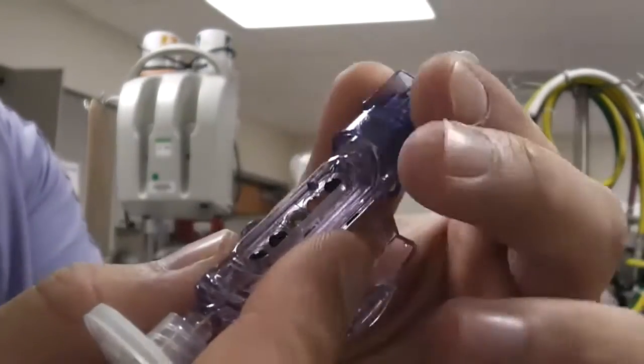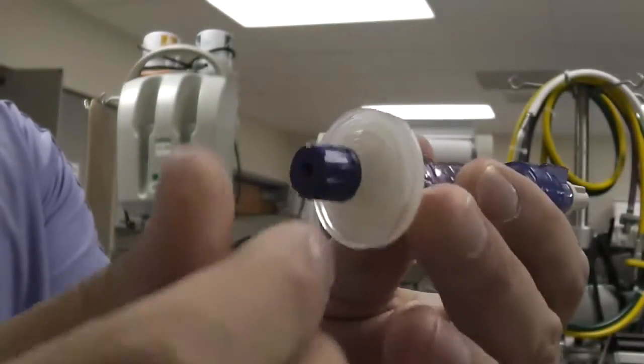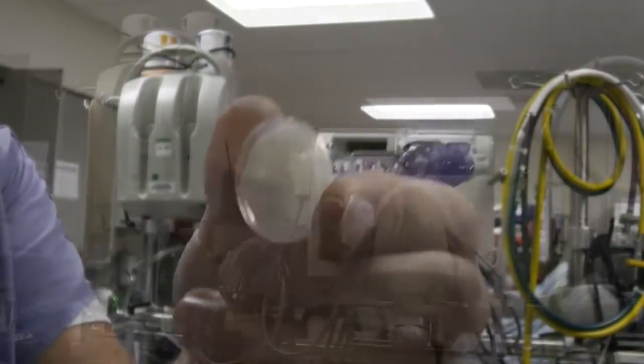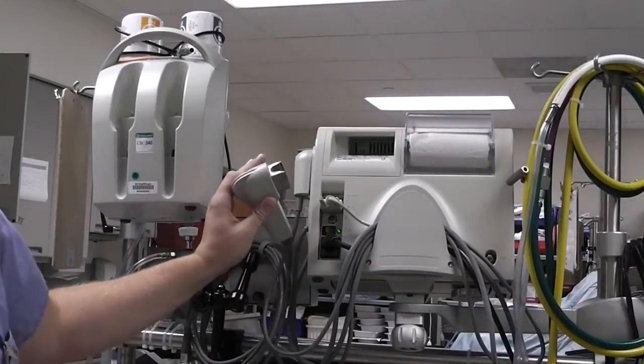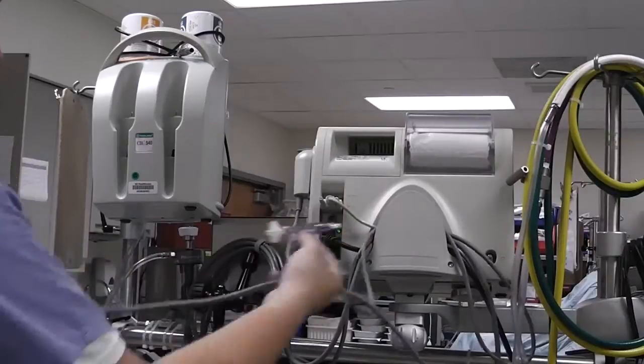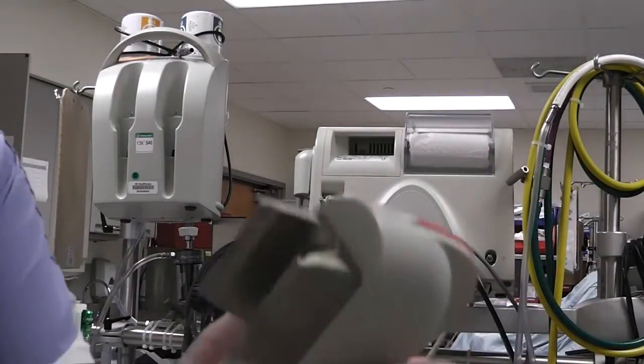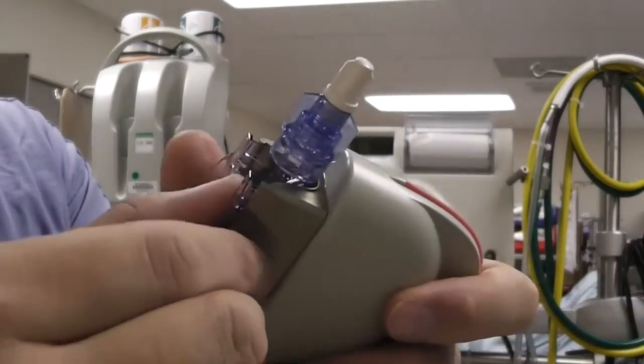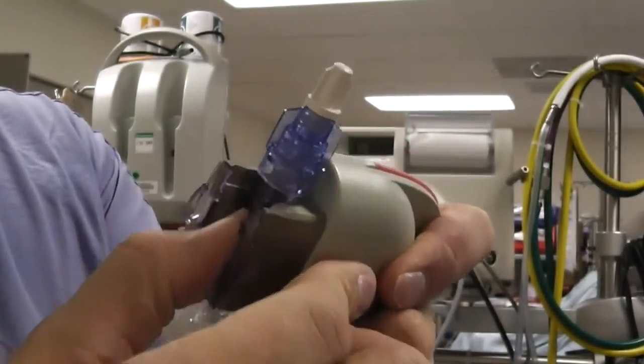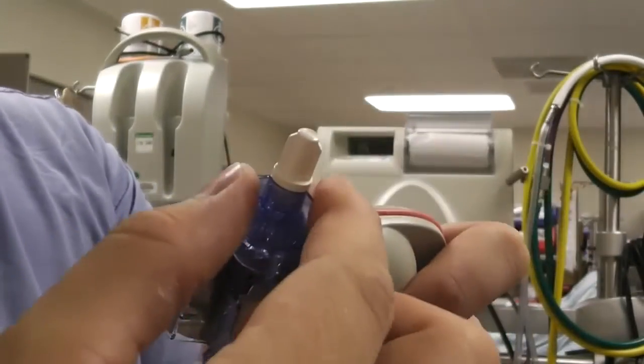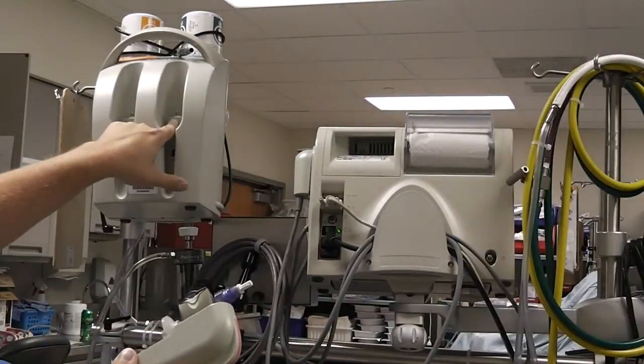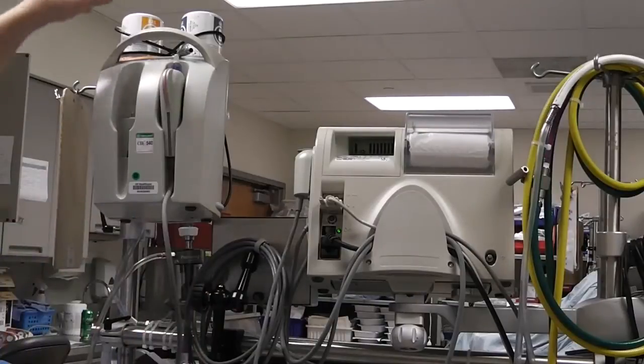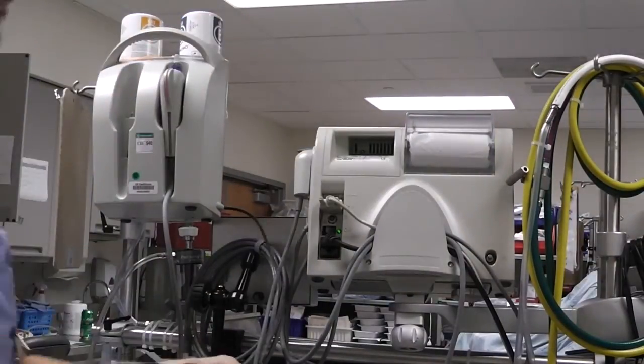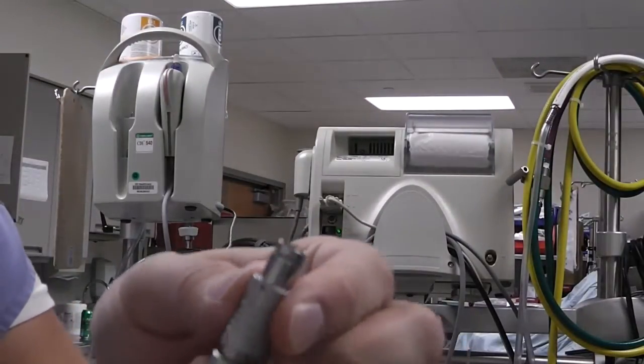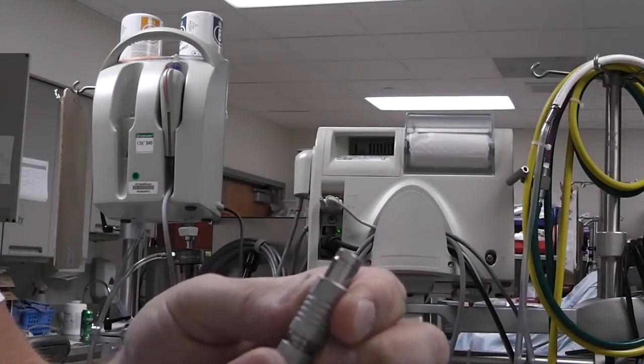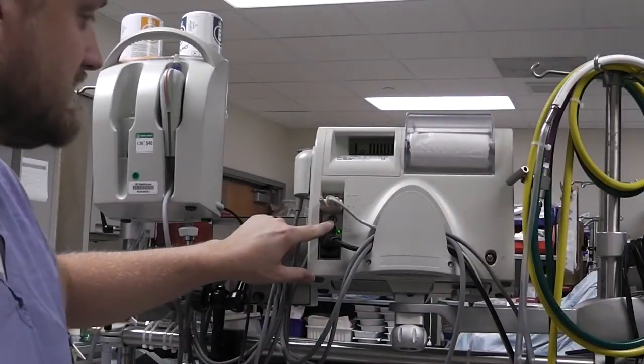We're going to slightly open this blue cap just so that it's loosened a little bit, and we're going to remove this blue cap from the bottom. We're going to remove the CDI attachment here, uncoil some cord, and push the sensor into this. I like to do it by pushing in the center. You'll hear it kind of click into place. Just make sure it's fully seated. The blue cap goes up, and now this gets seated into the back of the calibration equipment here. This black cable comes off the top. There is a red dot on it. I don't know if you can see that, but there's a red dot, and that orients to the left on the back of the CDI under this serial cable here.